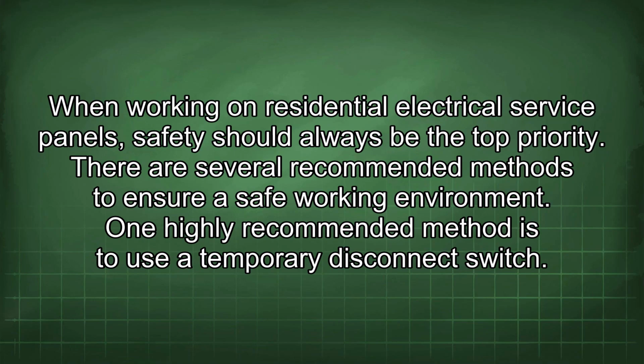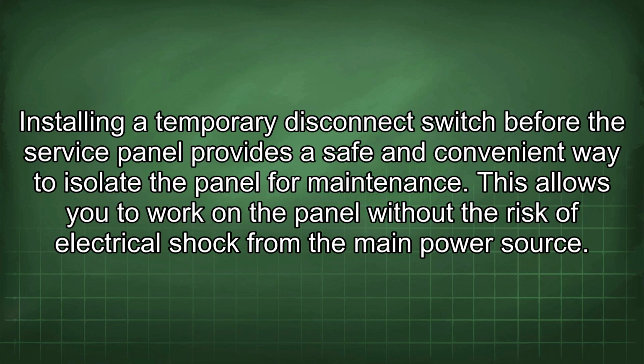When working on residential electrical service panels, safety should always be the top priority. There are several recommended methods to ensure a safe working environment. One highly recommended method is to use a temporary disconnect switch. Installing a temporary disconnect switch before the service panel provides a safe and convenient way to isolate the panel for maintenance. This allows you to work on the panel without the risk of electrical shock from the main power source.